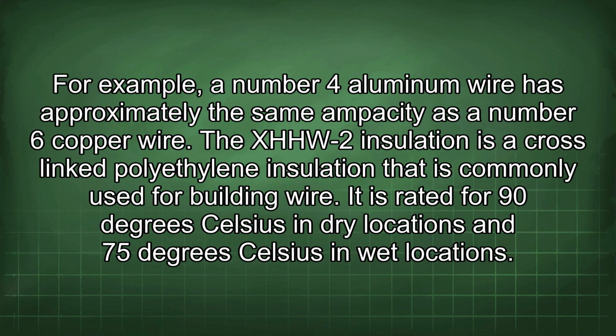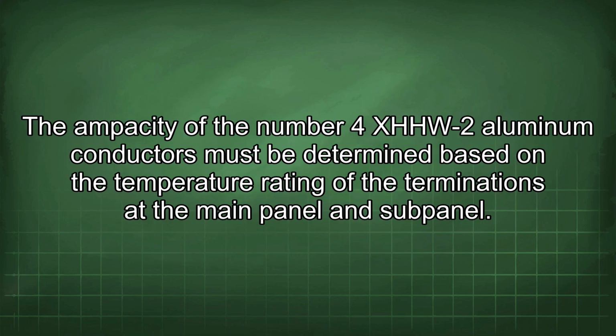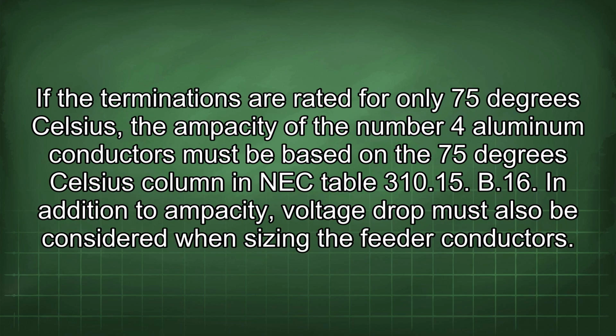For example, a number 4 aluminum wire has approximately the same ampacity as a number 6 copper wire. The XHHW-2 insulation is a cross-linked polyethylene insulation that is commonly used for building wire. It is rated for 90 degrees Celsius in dry locations and 75 degrees Celsius in wet locations. The ampacity of the number 4 XHHW-2 aluminum conductors must be determined based on the temperature rating of the terminations at the main panel and subpanel. If the terminations are rated for only 75 degrees Celsius, the ampacity of the number 4 aluminum conductors must be based on the 75 degrees Celsius column in NEC Table 310.15.